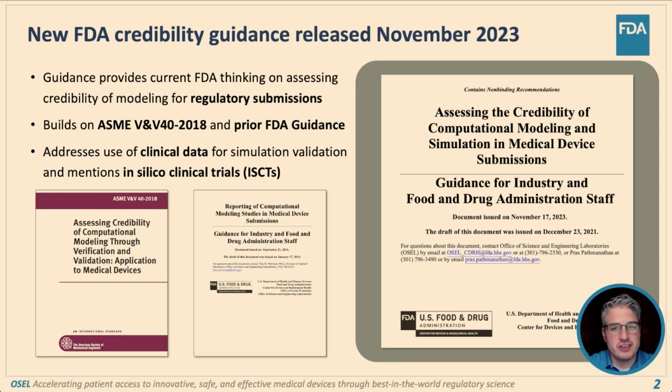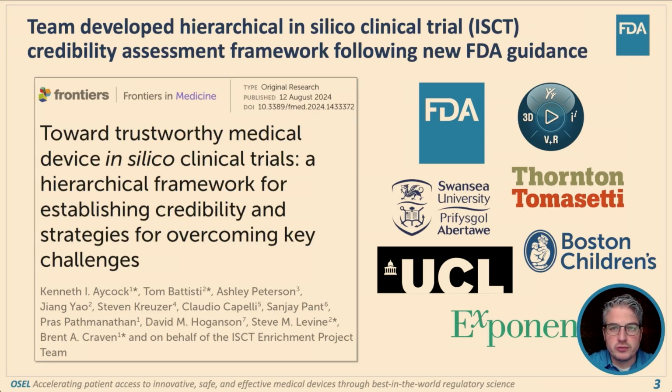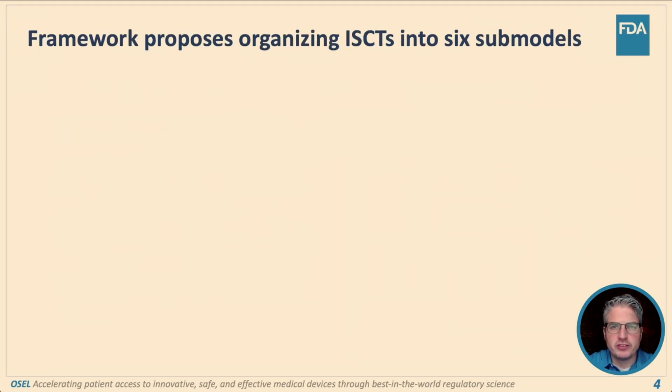However, the guidance does not address the specific challenges associated with assessing the credibility of a complex model like an in silico clinical trial, and it doesn't provide in silico clinical trial examples. Our team, with input from several advisory councils, developed a hierarchical framework for credibility assessment of in silico clinical trials for medical devices, which was recently published in Frontiers in Medicine and is openly available online. I will now briefly summarize the proposed hierarchical credibility assessment framework.